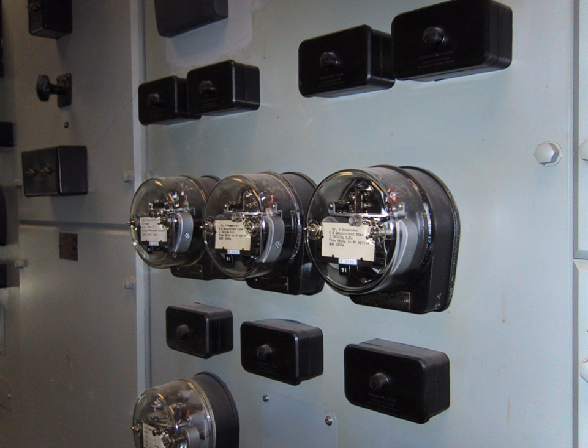A protective relay may respond to the magnitude of a quantity such as voltage or current. Induction relays can respond to the product of two quantities in two field coils, which could, for example, represent the power in a circuit. It is not practical to make a relay that develops a torque equal to the quotient of two AC quantities. This, however, is not important. The only significant condition for a relay is its setting, and the setting can be made to correspond to a ratio regardless of the component values over a wide range.